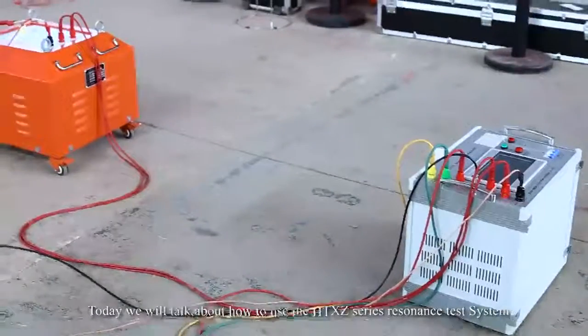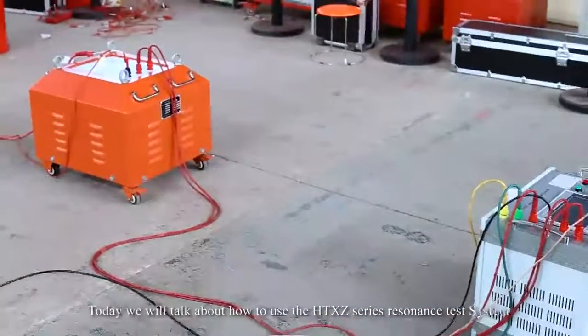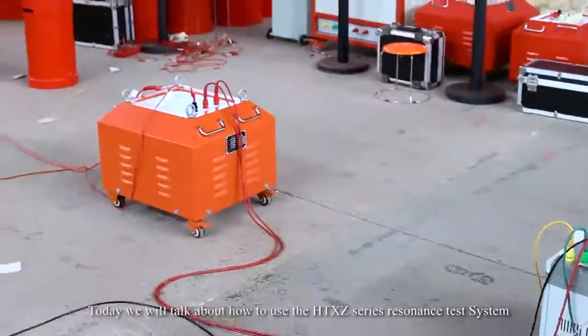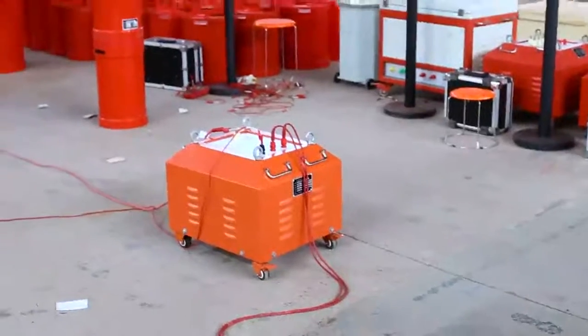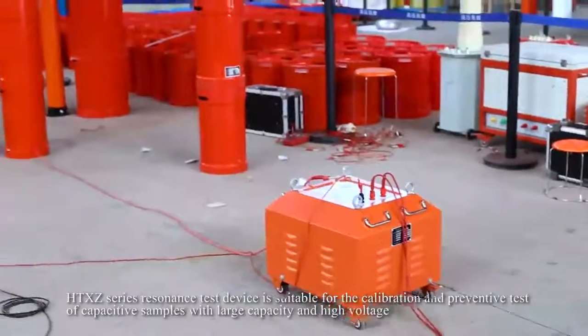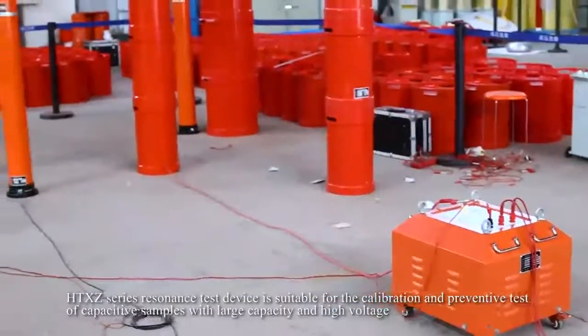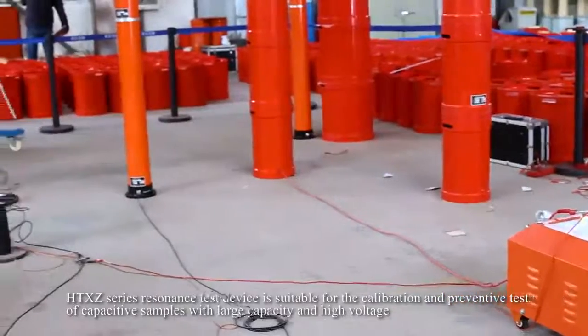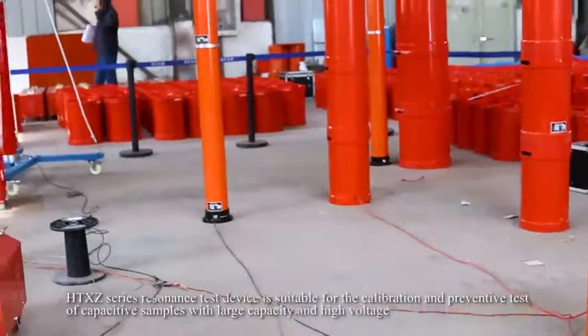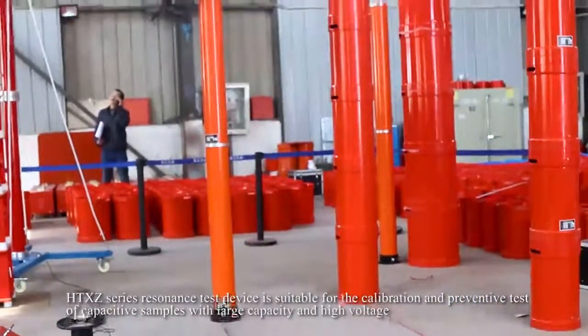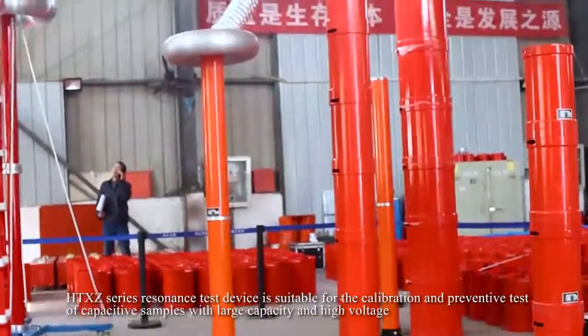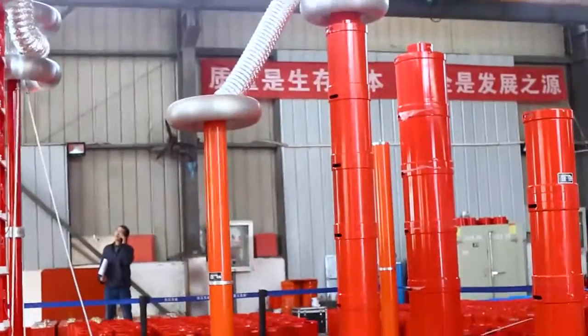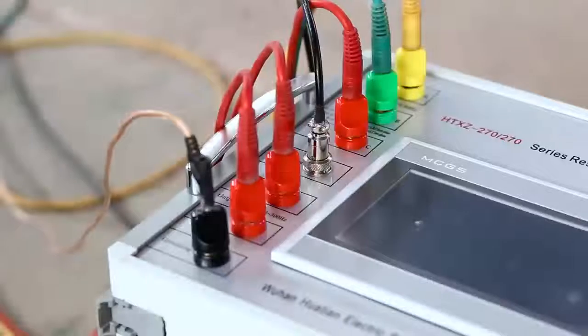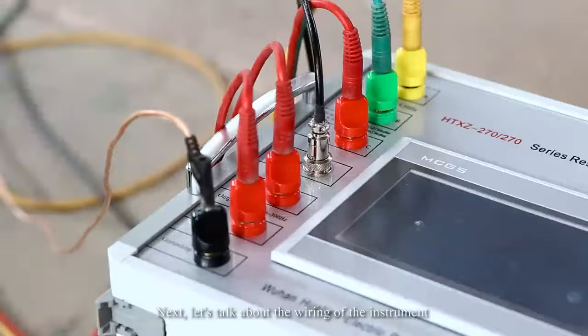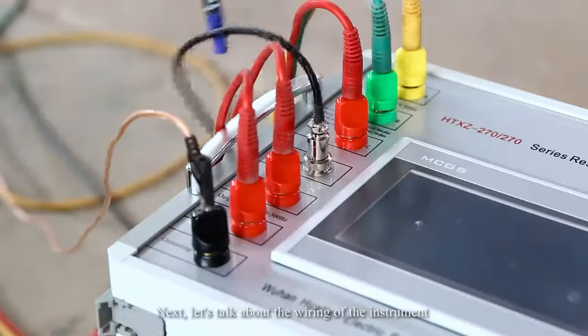Today we will talk about how to use the HTXZ Series Resonance Test System. The HTXZ Series Resonance Test Device is suitable for the calibration and preventive test of capacitive samples with large capacity and high voltage. Next, let's talk about the wiring of the instrument.